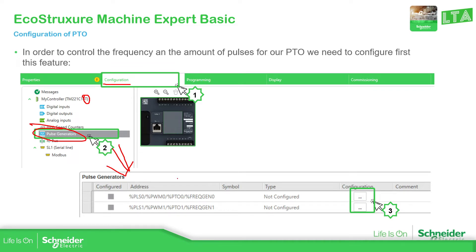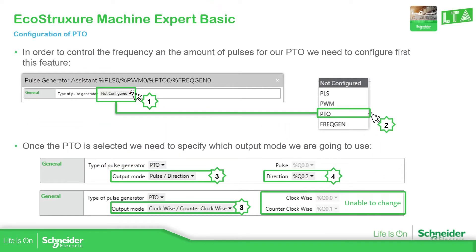Once we have the pulse generator option, we click on the square to access the configuration. When we select PTO output, it gives us the two modes. If you use clockwise/counterclockwise, you can see it uses both fast outputs on the controller. If you use pulse direction, it uses one fast output for the pulse, and the direction can be assigned to any other normal output.